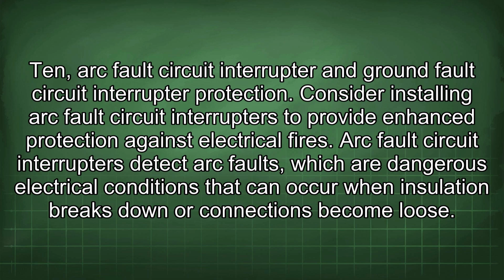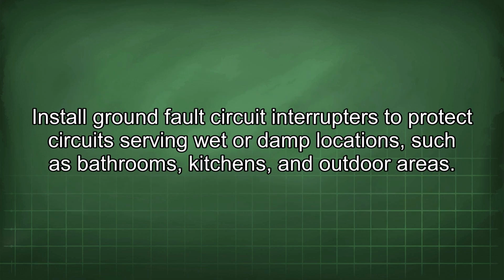10. Arc fault circuit interrupter and ground fault circuit interrupter protection. Consider installing arc fault circuit interrupters to provide enhanced protection against electrical fires. Arc fault circuit interrupters detect arc faults, which are dangerous electrical conditions that can occur when insulation breaks down or connections become loose. Install ground fault circuit interrupters to protect circuits serving wet or damp locations, such as bathrooms, kitchens, and outdoor areas.